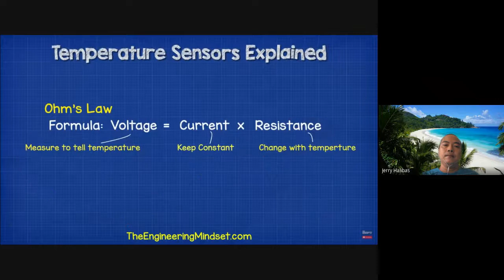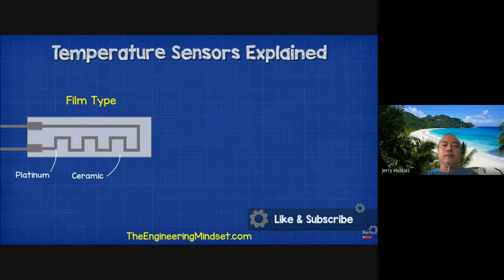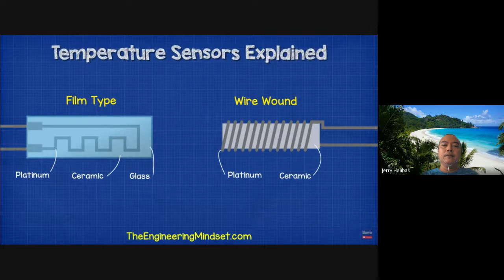For example, at 0 degrees Celsius, the material will have a resistance of 100 ohms, and at around 100 degrees Celsius, it will have a resistance of 138.5 ohms. There are some different designs for these types, but they're typically either film type, where the platinum is coated onto a ceramic plate into a pattern and then the whole thing is sealed in glass, or it will be a platinum wire, which is wound around a ceramic core. Again, this will be sealed in glass for protection.